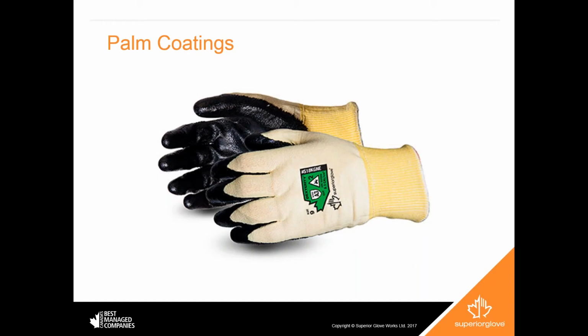Matt? Yeah, and I'm glad that you bring up that neoprene palm coating. Basically, when a glove is tested for arc flash, it's tested based on the least protective area. So that's usually going to be like the back of the hand. So the S18 KGNE was rated at an ATPV of 8.2 calories per centimeter squared. But the neoprene palm coating can get up to about 50 calories per centimeter squared of protection. So your palm coatings are really good news for industries that are facing the hazard of arc flash, because your palm and your fingertips in the event of an arc flash are going to be some of the areas most affected. So it's really good to have that little bit of extra protection where you need it the most.